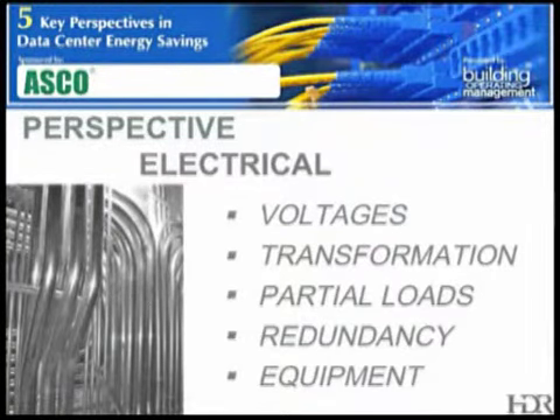Some of the drawbacks, though, when we implement those are we can increase the harmonics further upstream because we've gotten rid of the transformers, and now we're not consuming those harmonics in the delta Y side. And then we still need 120 volt power for housekeeping loads or other tertiary loads that we have out there. And some of the distribution equipment is not widely applied in the U.S. It's available, but not widely applied. So you may have issues with your maintenance staff or with the local contractors there.